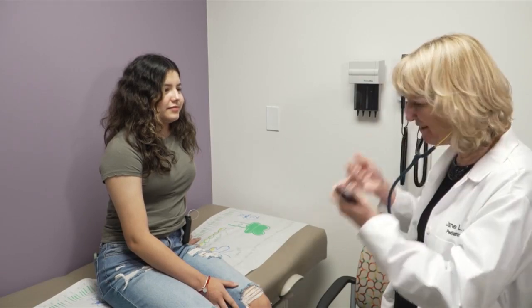I actually have the iLet here. She will put this on, will plug in her weight, and within four days it will conservatively give her insulin, figure out her schedule, and keep her blood sugars in the 200s, then 150s, and then down to 140s.